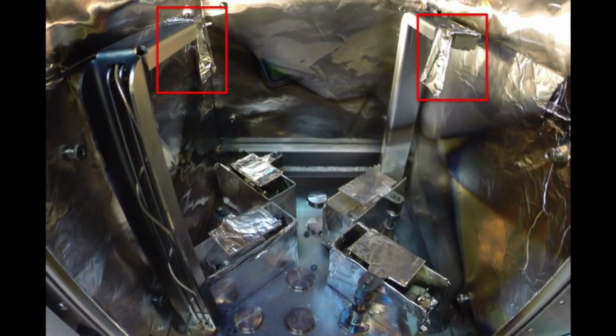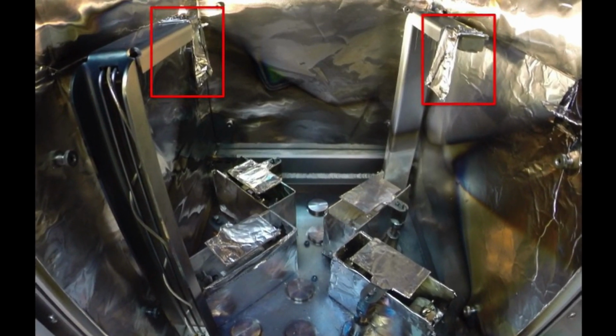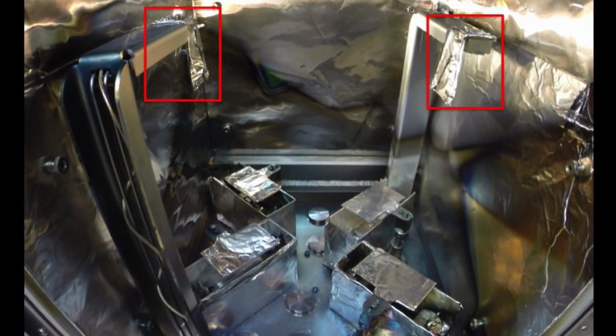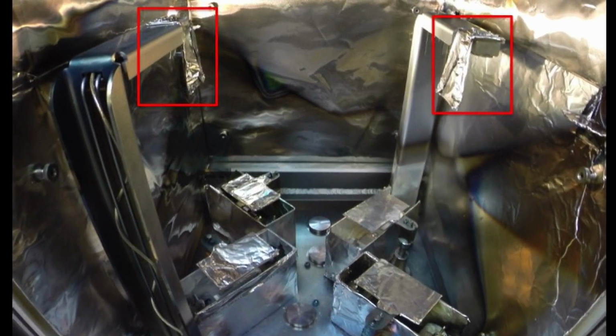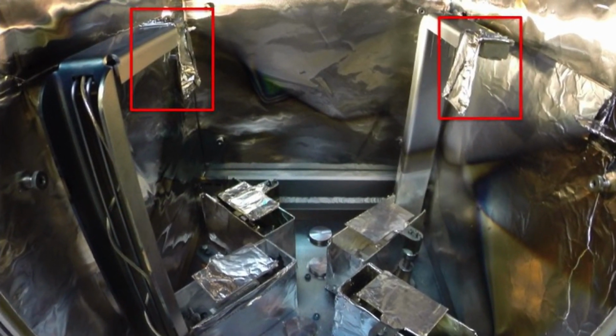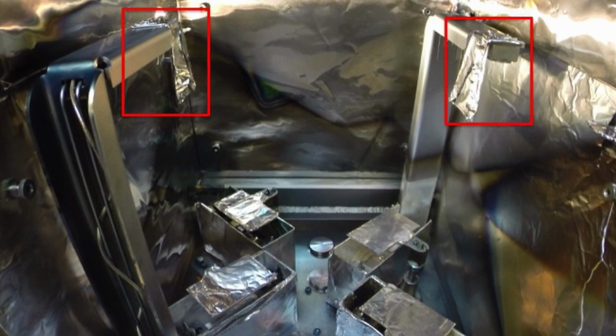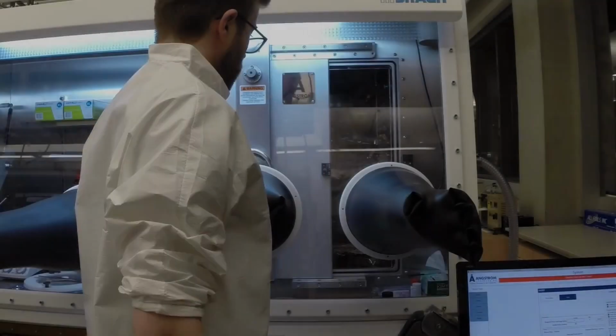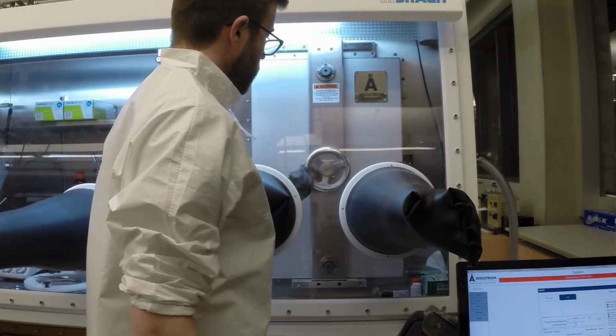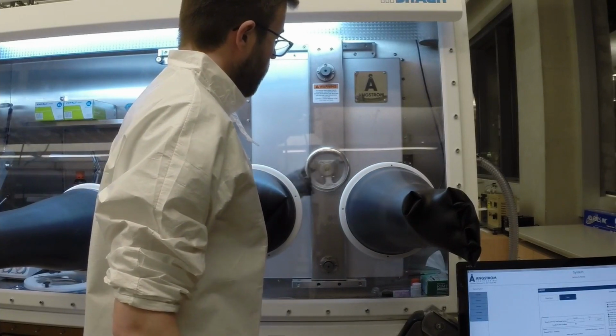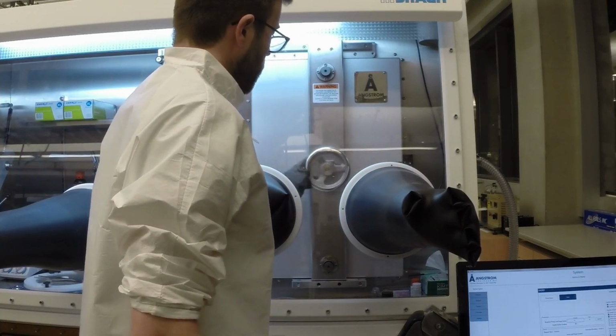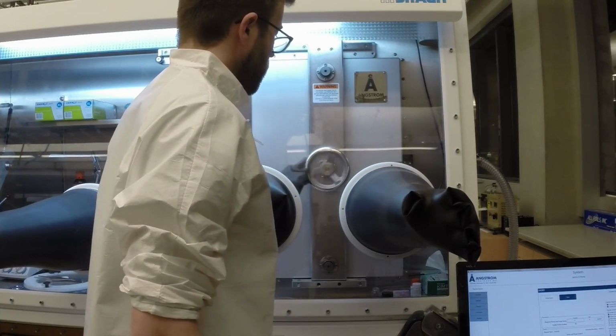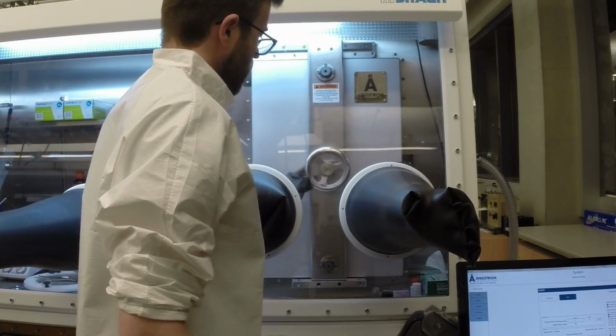Before we pump down, I'd like to point out there are two quartz crystal microbalance sensors that measure the rate of material deposited. This sensor is calibrated by measuring film thickness with a profilometer after evaporation. Anyways, after loading substrates and all deposition materials, the door is closed and the chamber is pumped down to 10 to the minus 6 torr.